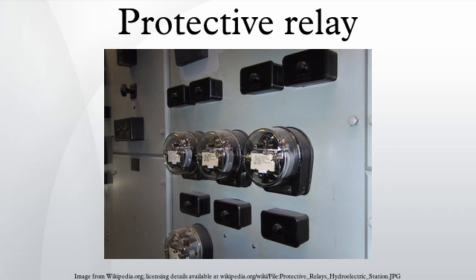Often, differential protection relays will have a rising characteristic to make the operating set point a function of the through current. The higher the current in the line, the larger the differential current required for the relay to detect a fault. This is required due to the mismatches in current transformers. Small errors will increase as current increases to the point where the error could cause a false trip, if the current differential relay only had an upper limit instead of a rising differential characteristic. Current transformers have a point where the core saturates and the current in the CT is no longer proportional to the current in the line. A CT can become inaccurate or even saturate because of a fault outside of its protected zone where the CTs see a large magnitude but still in the same direction.